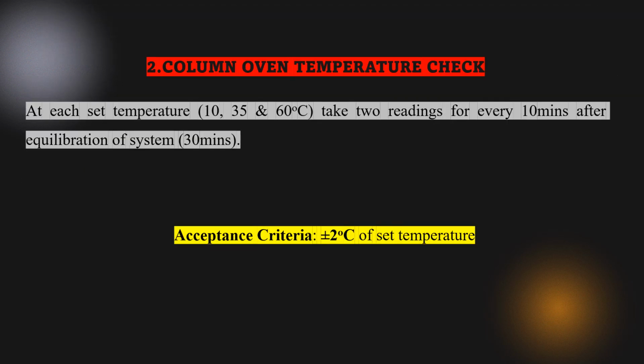Now the second part that needs to be calibrated in HPLC is your column oven temperature, because in HPLC analysis this also plays a crucial part in separation of the analytes. So the set temperature could be 10 degrees Celsius, 35 degrees Celsius, 60 degrees Celsius, and you need to take 2 readings. And the acceptance criteria for this is plus minus 2 degrees Celsius of the set temperature.